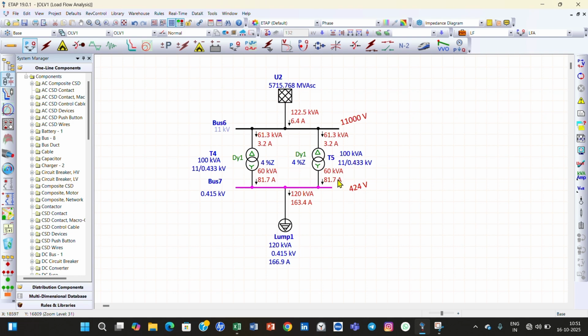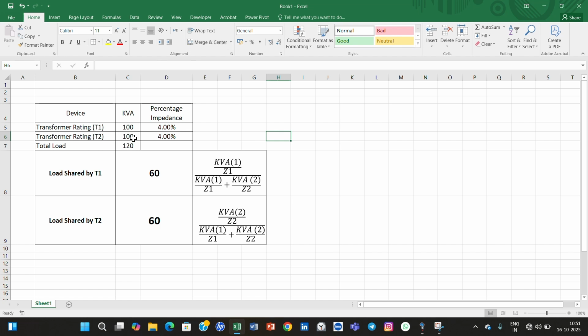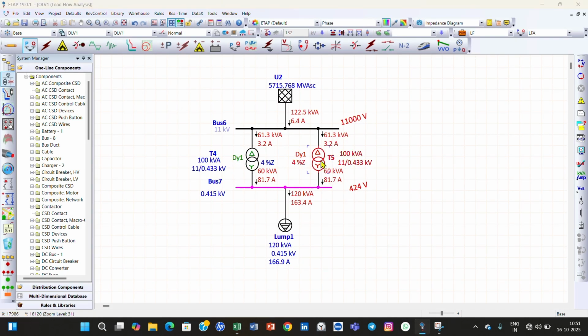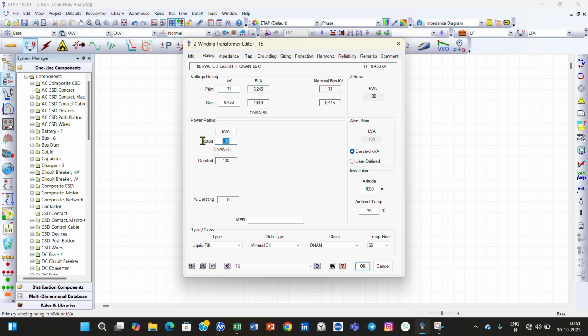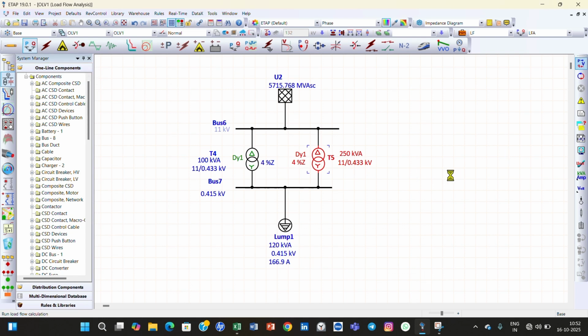Now we can change the rating of the second transformer to 250 kVA, keeping the percentage impedance the same. You can see the load shared by transformer one is 85.71 and by transformer two is 34.29. Now we check the ETAP results. We change the transformer rating here to 250 kVA, click OK, and then perform the load flow analysis. You can see transformer one shares 34.3, that is 34.29, the same, and 85.71, that is 85.7, the same. So our manual calculation is completely matching with the ETAP results.